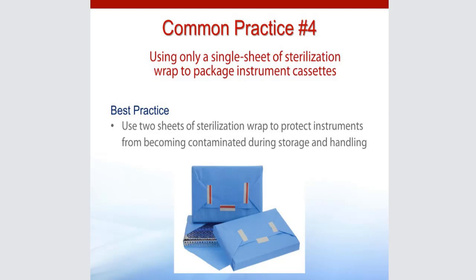The size of the tape piece should be about 4 inches in length for the average dental and dental hygiene cassettes. And so you're going to put 2 pieces at the ends to hold the end pieces, and then 1 piece across the middle. So again, 4 inches, not a tiny little 1-inch piece of tape. You need to use the whole 4 inches, because remember, that is going to be put under pressure and steam, and if you don't have it secured well, that's going to pop up and it's not going to be sealed.